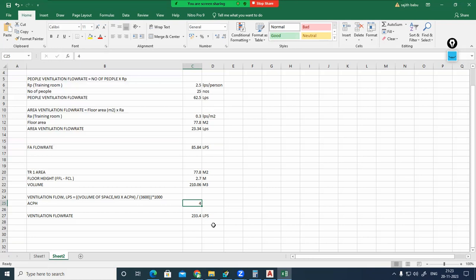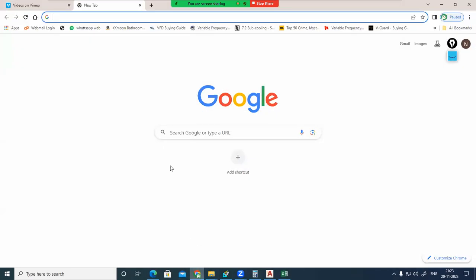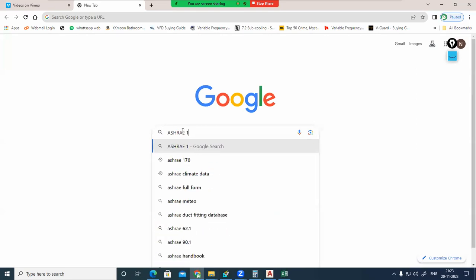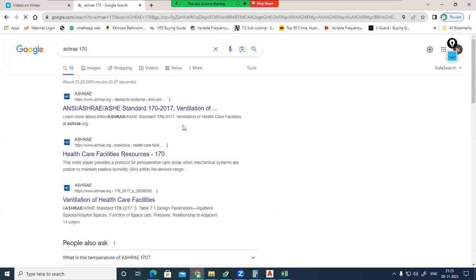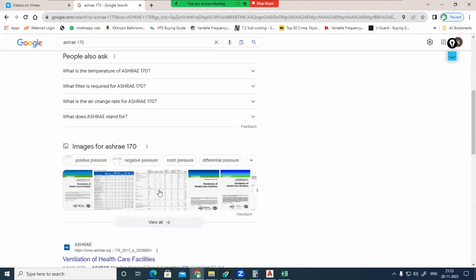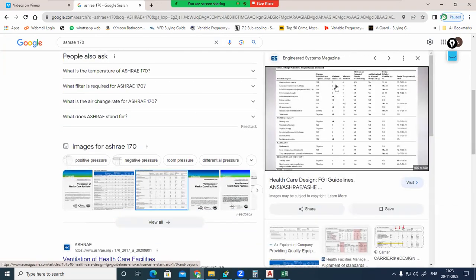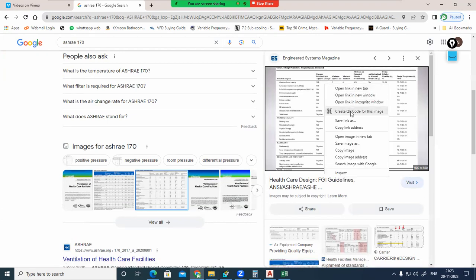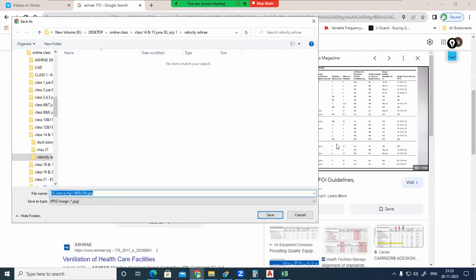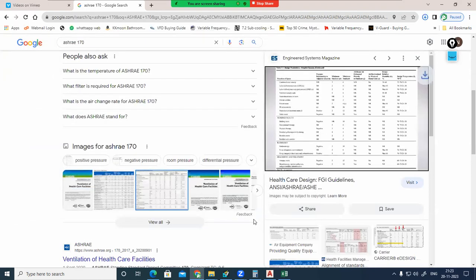But with respect to the local standard for healthcare, they have the ASHRAE 170 standard, I guess. Yeah, ASHRAE 170, one second. ASHRAE 170, ventilation for healthcare facilities, exactly. From this standard, we can find the data on how much fresh air has to be provided. For example, minimum outdoor ACH. You might be able to see this, right? Save image in downloads. Let me download it. Save this one.